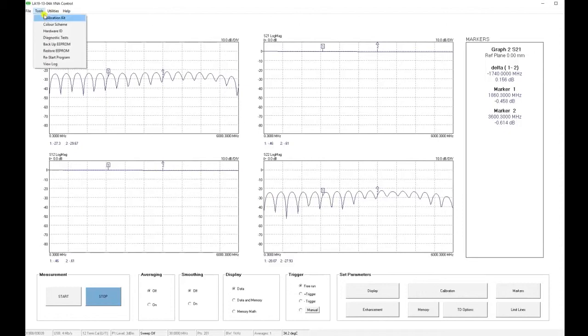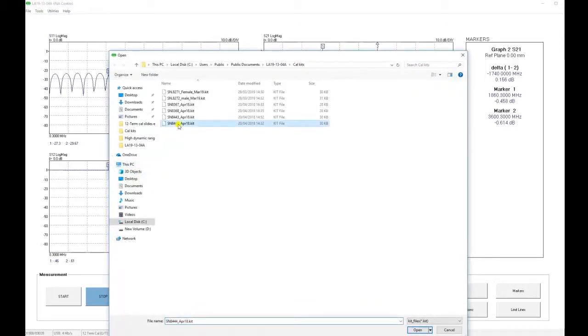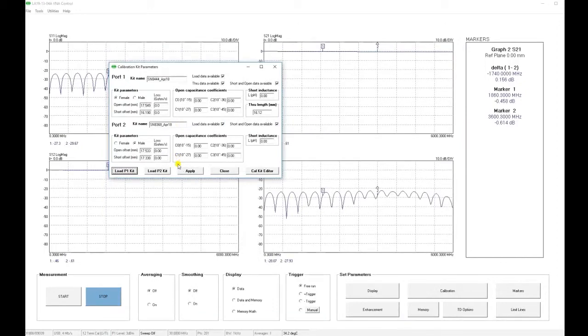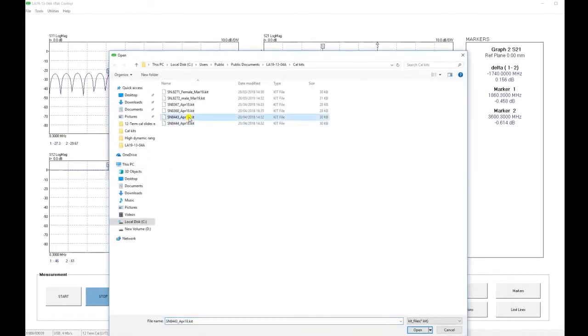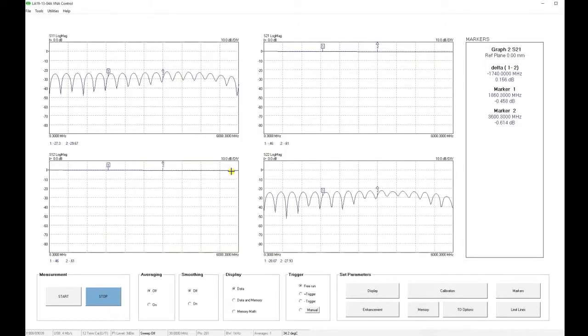The first thing we need to do is to select our calibration kits. We are going to use the serial number 8444 kit on port 1, that's a female kit, and the male kit 8443 on port 2. We load those kits, and we are ready to begin our calibration.